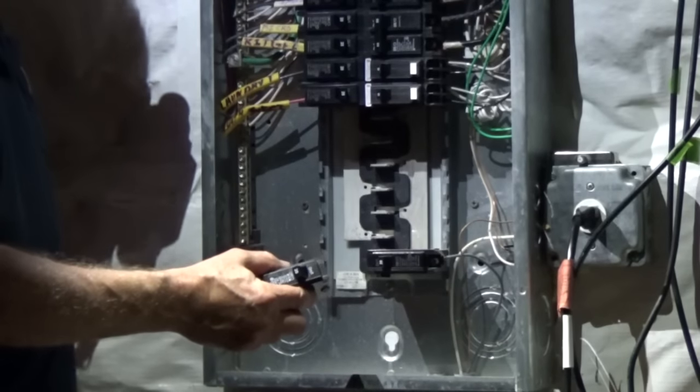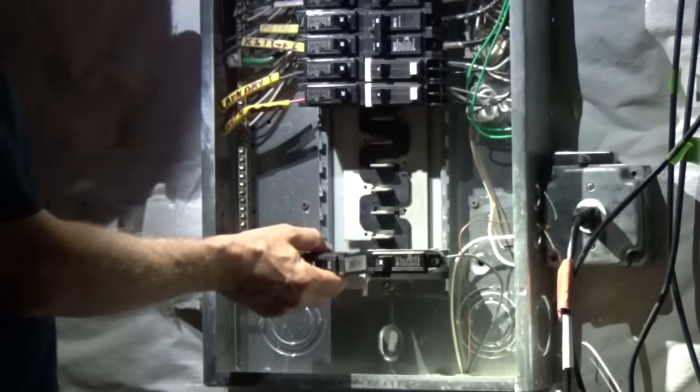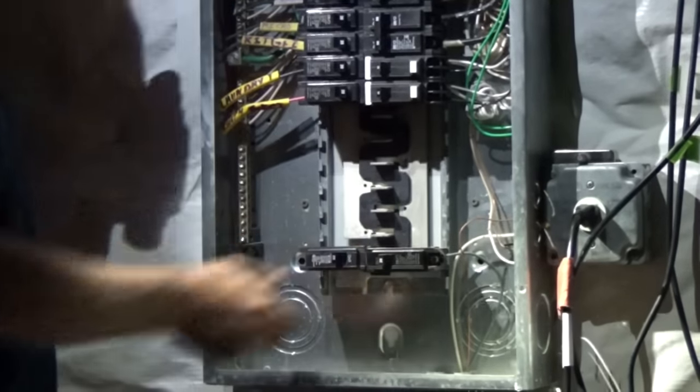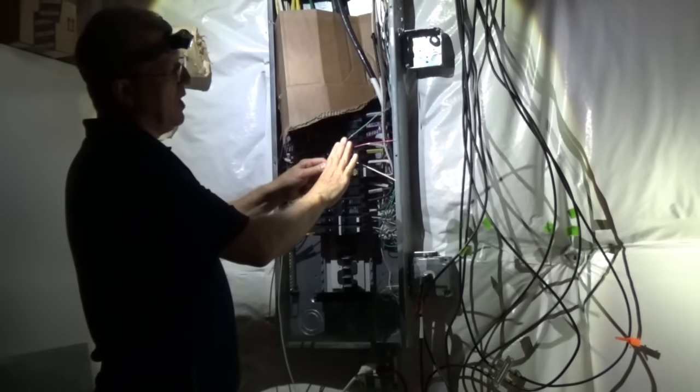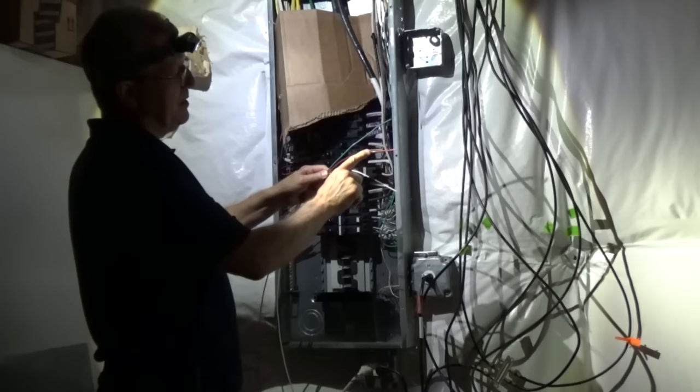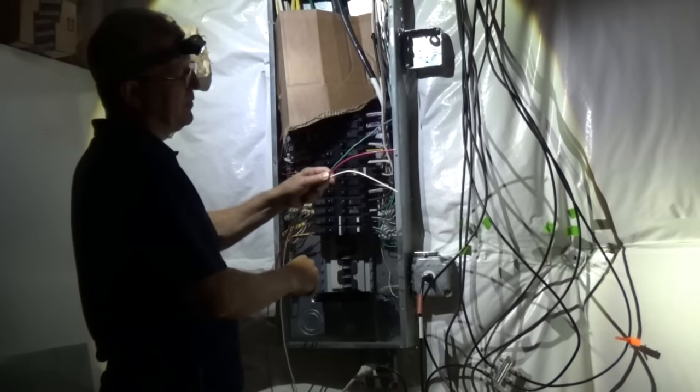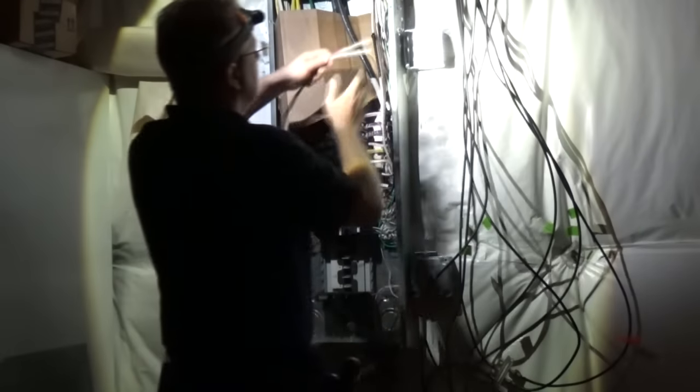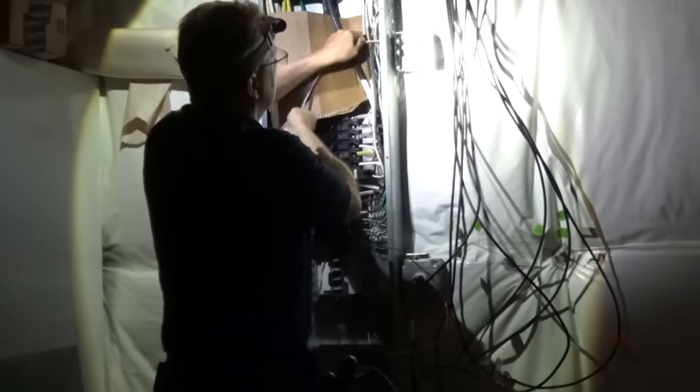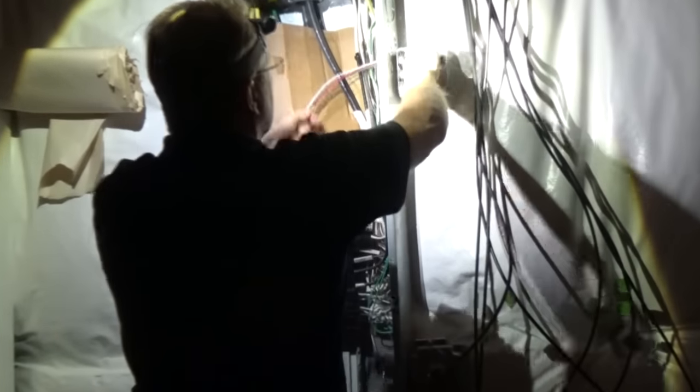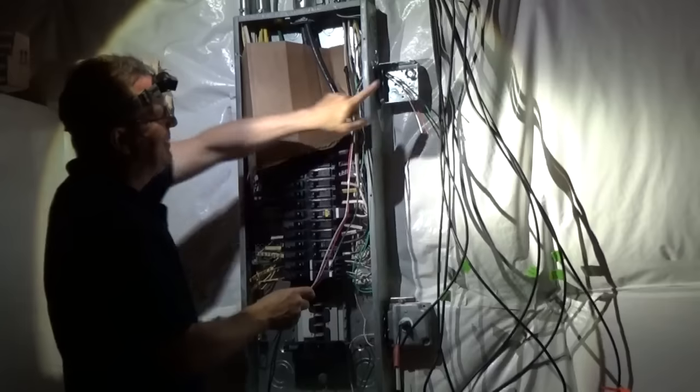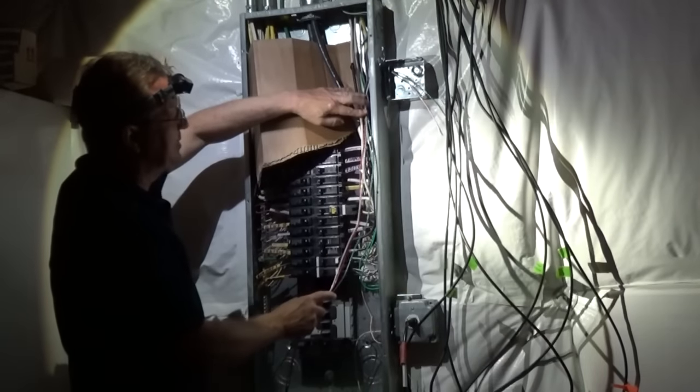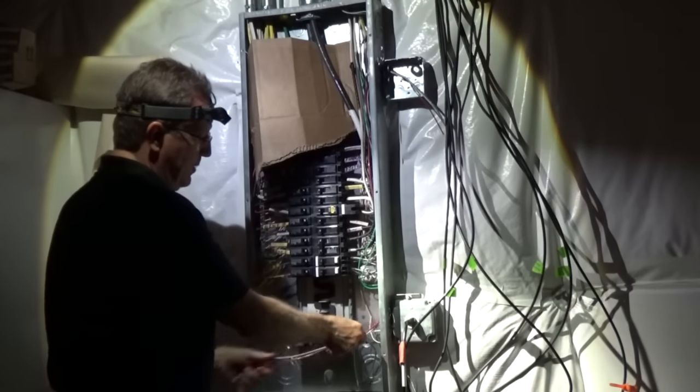I'm going to add my new 20-amp breaker to the breaker bus bar. Now I'm going to run my wire into the box. I'm using 12-gauge wire for this 20-amp circuit. My red wire is hot, my green for ground, and white for neutral. I'm leaving six or seven inches exposed out of the box, and I'm laying the wire inside the electric panel.